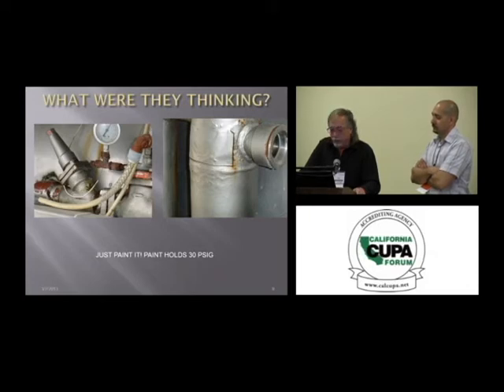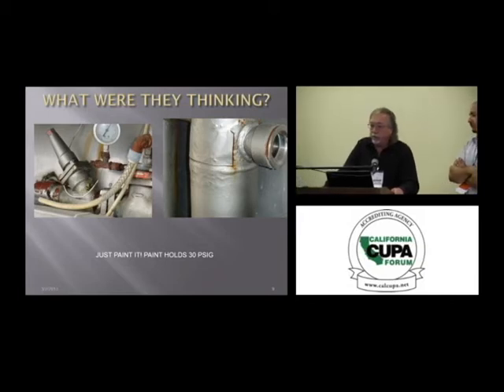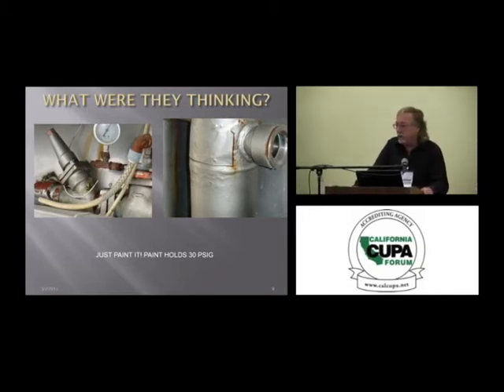Now, if the pitting's not too bad, we'll clean it to bare metal, paint it, and recover it with insulation if it's insulated. But if it's questionable, if the pitting's too deep, then we'll bring in non-destructive testing. We do not use NDT in this industry on all the piping and vessels that we work with because, again, ammonia facilities rot from the outside in, not the inside out. When we see a suspect plant, though, then we'll recommend the additional non-destructive testing. Typically, the money's better spent repairing what you find visually and repairing the insulation. If you see rust coming through piping, through coatings or insulation on piping, you know you have corrosion going on underneath.